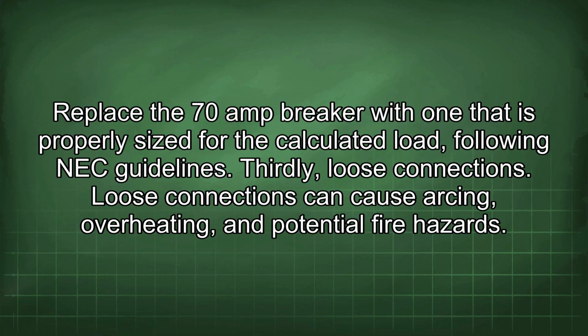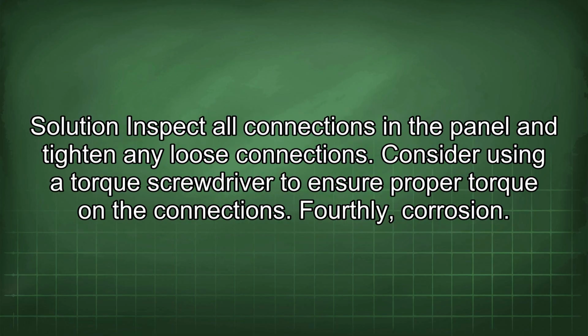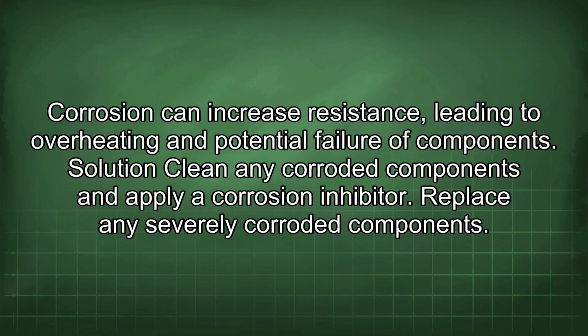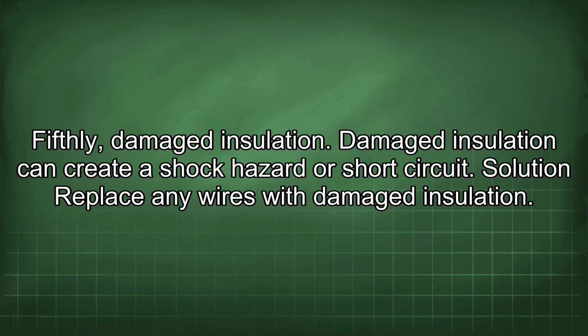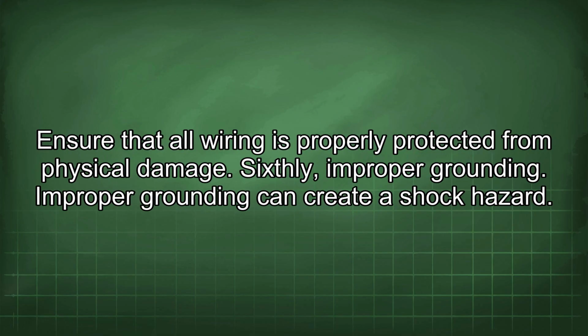Thirdly, loose connections. Loose connections can cause arcing, overheating, and potential fire hazards. Solution: inspect all connections in the panel and tighten any loose connections. Consider using a torque screwdriver to ensure proper torque on the connections. Fourthly, corrosion. Corrosion can increase resistance, leading to overheating and potential failure of components. Solution: clean any corroded components and apply a corrosion inhibitor. Replace any severely corroded components. Fifthly, damaged insulation. Damaged insulation can create a shock hazard or short circuit. Solution: replace any wires with damaged insulation. Ensure that all wiring is properly protected from physical damage. Sixthly, improper grounding.